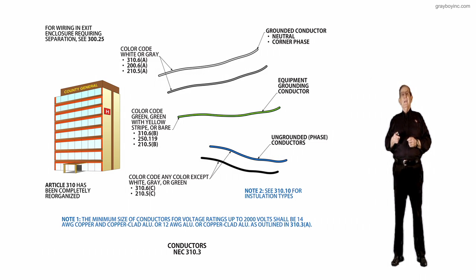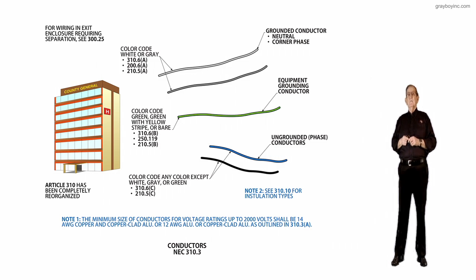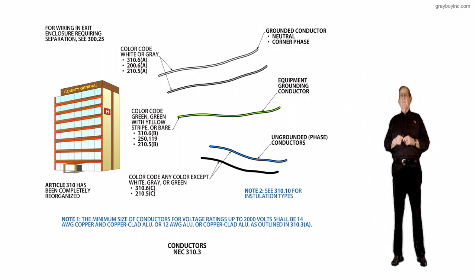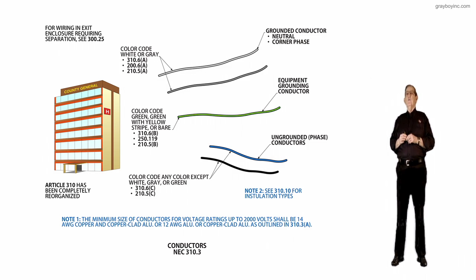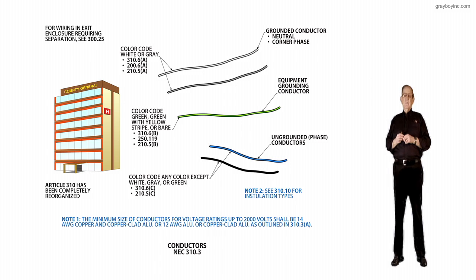For wiring in an exit enclosure requiring separation, remember we looked at that, we'll review it, 300.25. But now I would remind you that if you're looking at wiring in air handlers, such as under raised floors and so forth, look at 300.22 C, D and 645.4 and 5E.